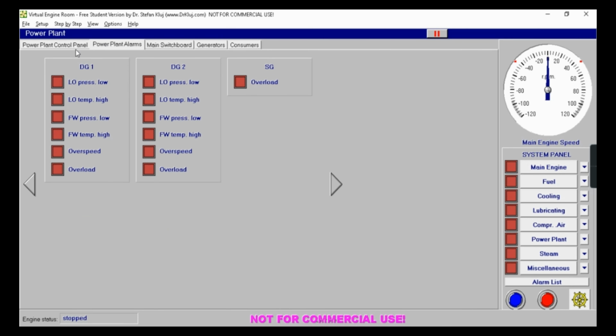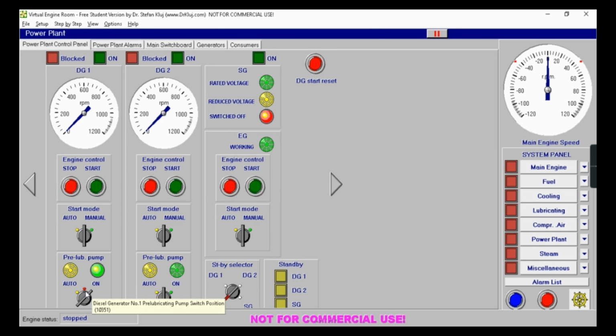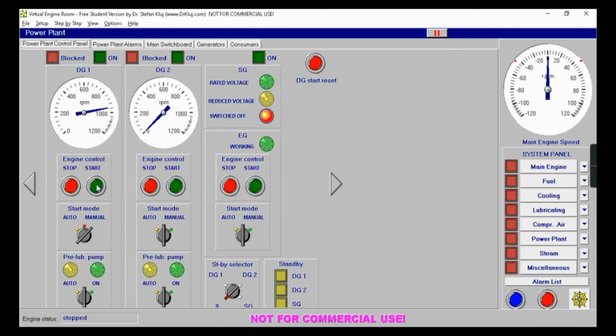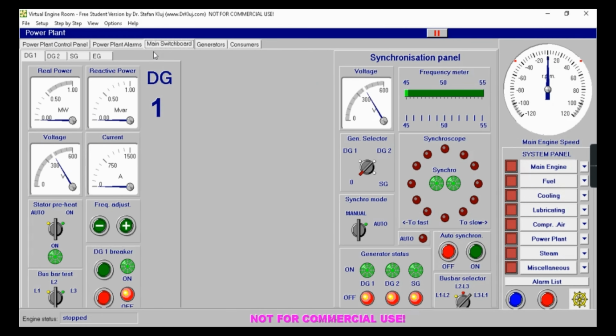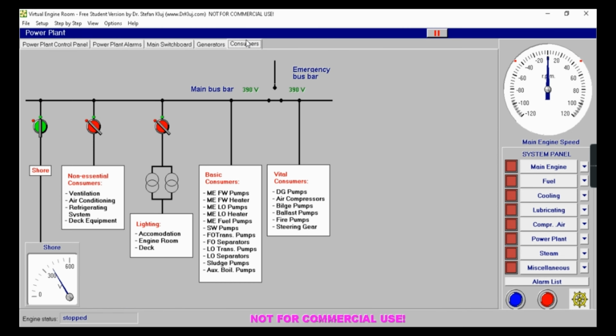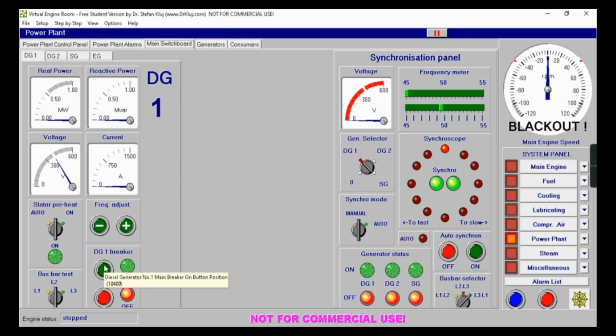Then switch on the pre-lubricating pump and set the mode into manual. Start button should be pressed until the generator will start. We will now connect the diesel generator to bus bars. Then switch off the shore connection. The start button for DG1 should be pressed.